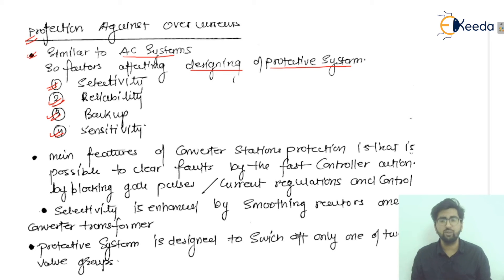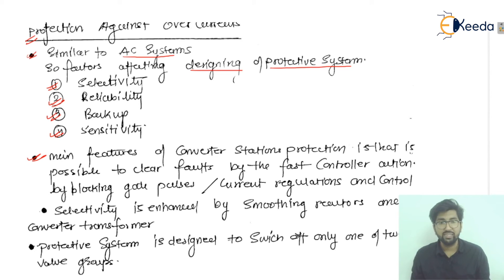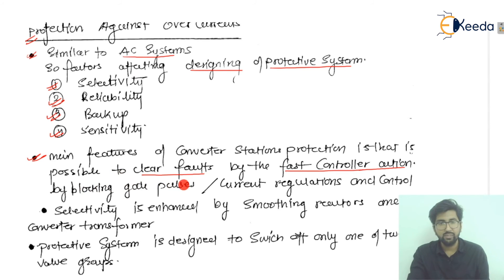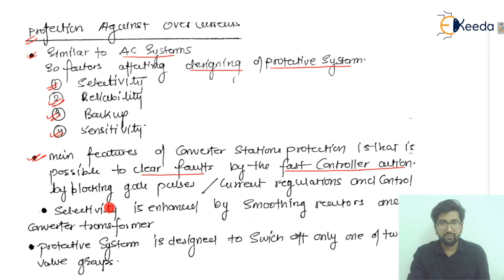Now the main features of converter station protection: it is possible to clear the fault by fast controller action — in milliseconds and microseconds — by blocking the gate pulses. If we block the gate pulses within a short duration of time, that is called current regulation and current control. These are the main features related with the protection schemes.